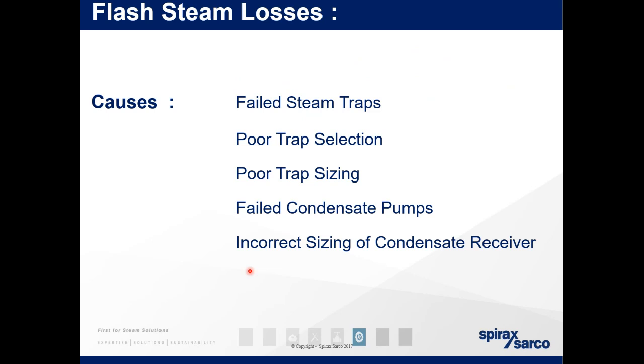Okay, for the last question: can you provide examples of applications where flash steam is used effectively? Yeah, so say you have a CRU which is open to atmosphere. So you see that pipe on the roof and it's venting. You could use a flash recovery vessel to grab that steam and maybe pull it through, say, a heat exchanger or combine it with motive steam and use it in a process.